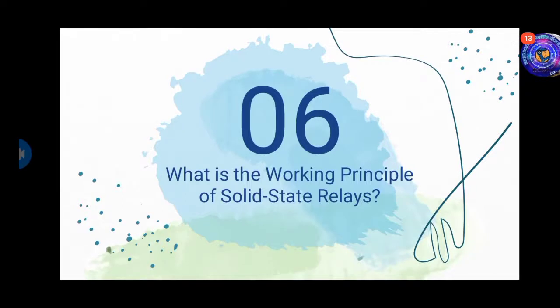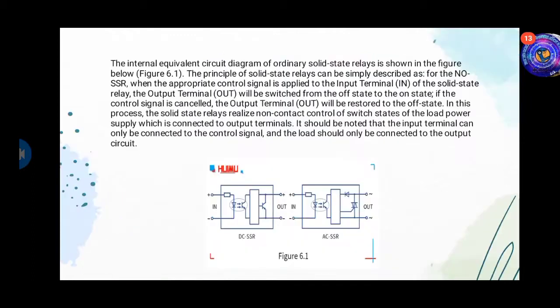So, what is the working principle of a solid-state relay? The internal equivalent circuit diagram of an ordinary solid-state relay is shown in figure 6.1 below. The principle of the solid-state relay can be simply described as follows: when the appropriate control signal is applied at the input terminal of the solid-state relay, the output terminal will switch from the off state to the on state. If the control signal is cancelled, the output terminal will be restored to the off state.